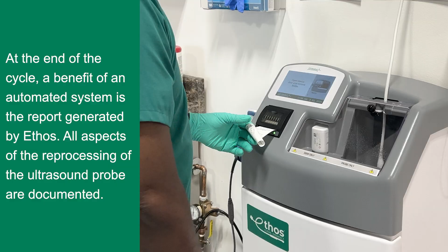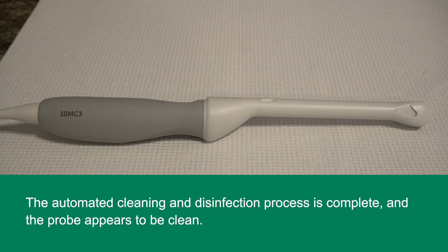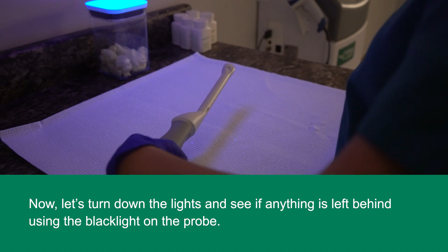At the end of the cycle, a benefit of an automated system is the report generated by Ethos. All aspects of the reprocessing of the ultrasound probe are documented. The automated cleaning and disinfection process is complete, and the probe appears to be clean. Now let's turn down the lights and see if anything is left behind using black light on the probe.